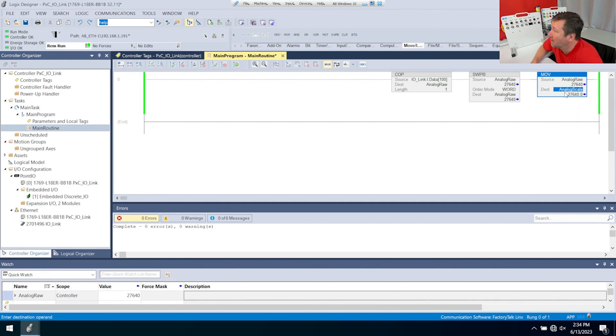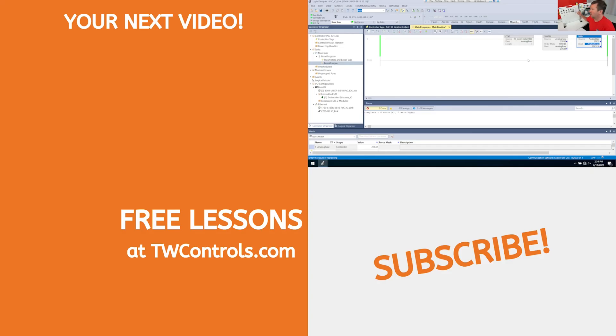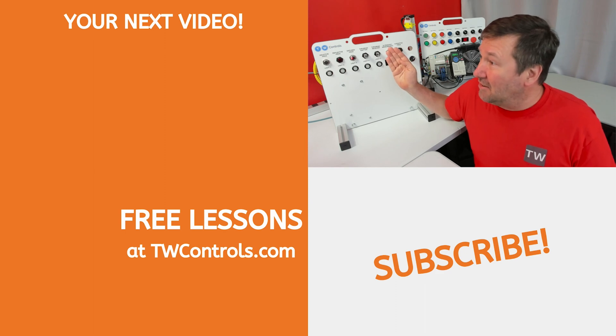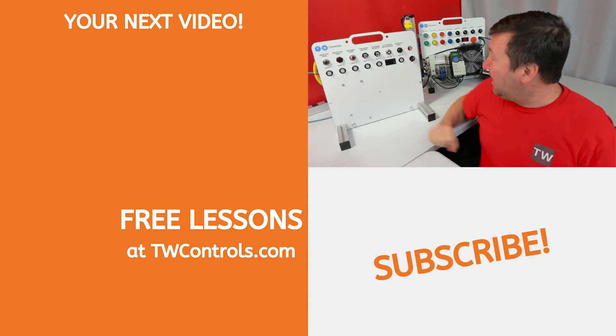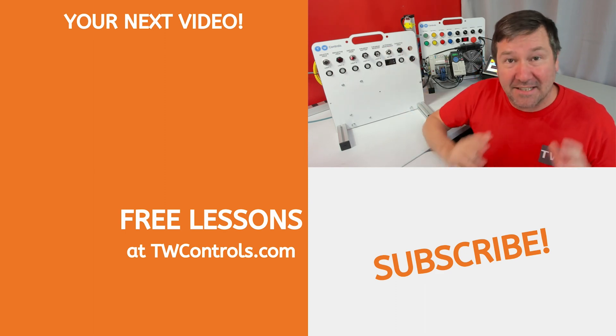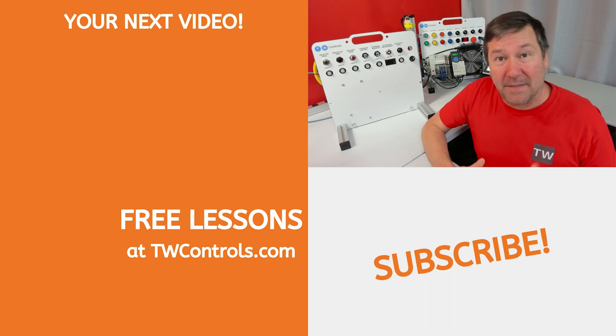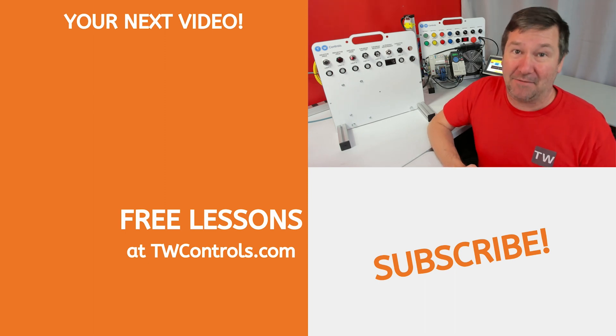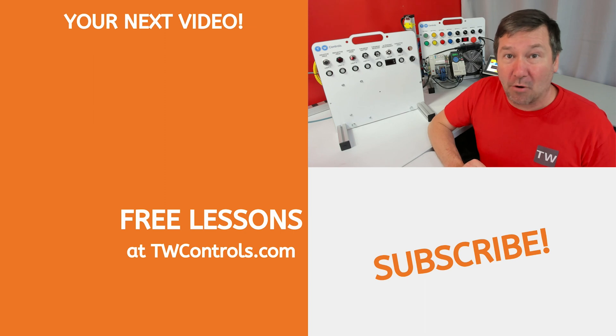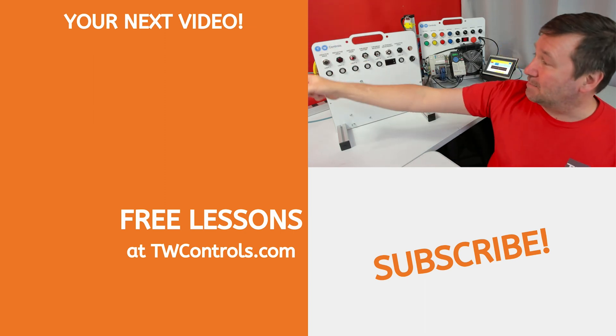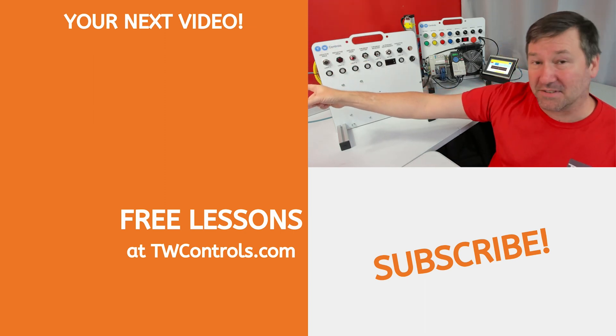Analog scale is going to have it in the correct order. If I slowly bring the sensor in, you see it's going to nicely and linearly go down now. We're ready to scale it to our engineering units. In the case of this ultrasonic sensor, it's going to be 30 millimeters to 350 millimeters. We have a lot of videos on scaling for analog signals, and I've created this playlist right here with some helpful tips.